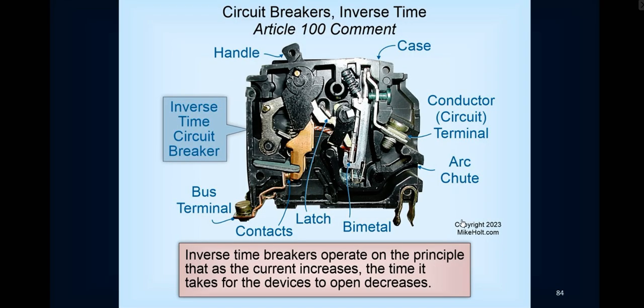And here's a circuit breaker. I don't know if you've ever seen a breaker like that. Notice, if you saw a ground fault breaker or an arc fault breaker, there'd be circuit boards inside of it. This is a mechanical device. Notice the arc chute in the back. And if you've ever had a dead short or something like that, that's pretty much where the fire comes out. That's what it's for.